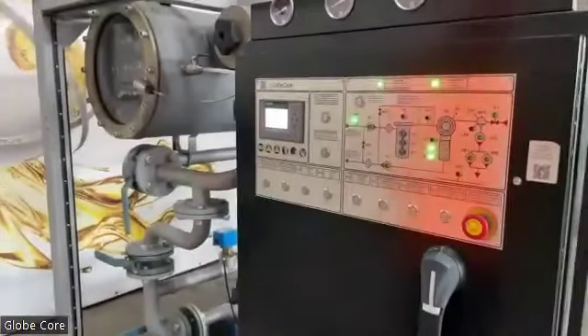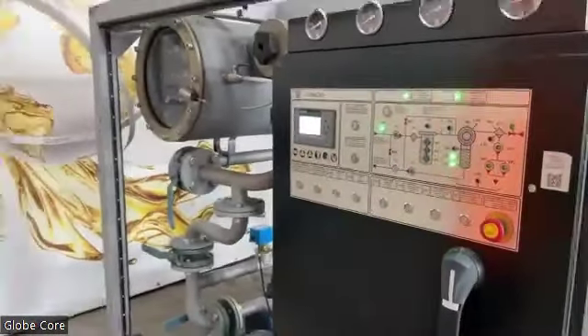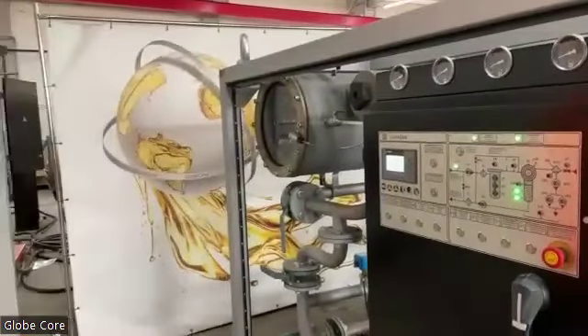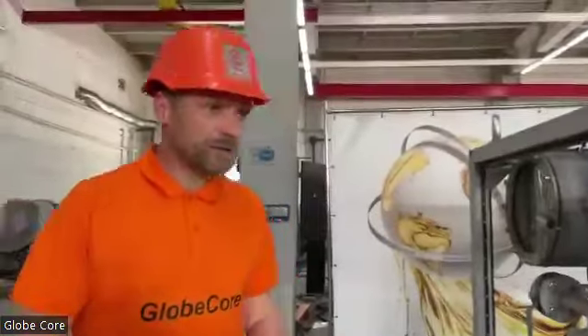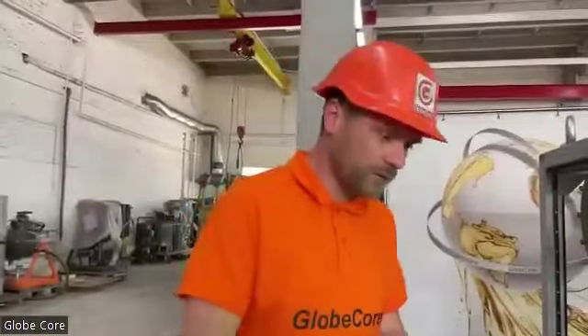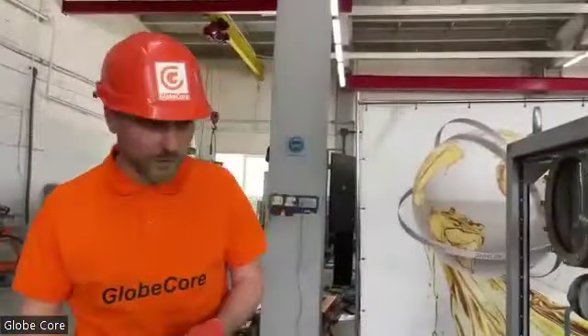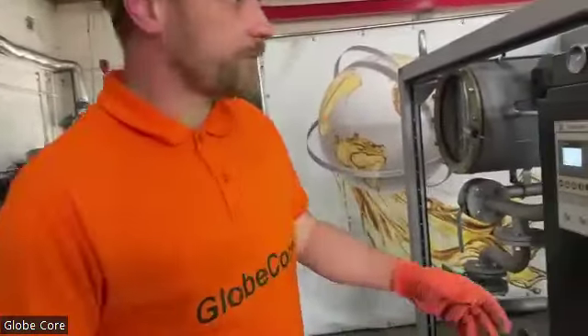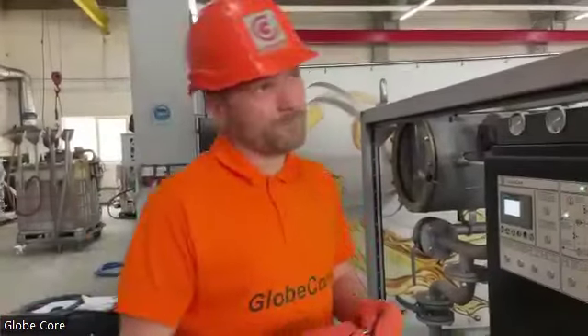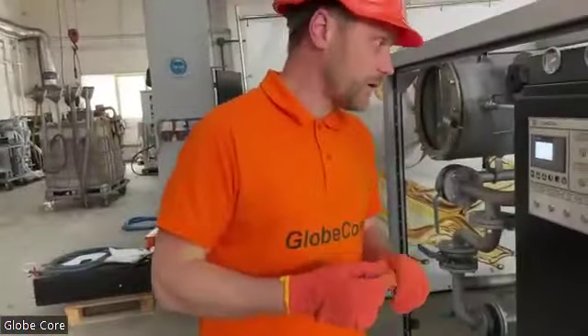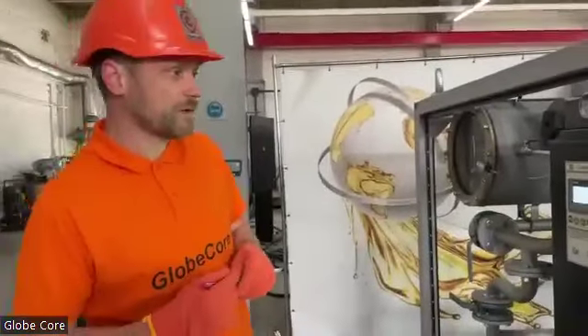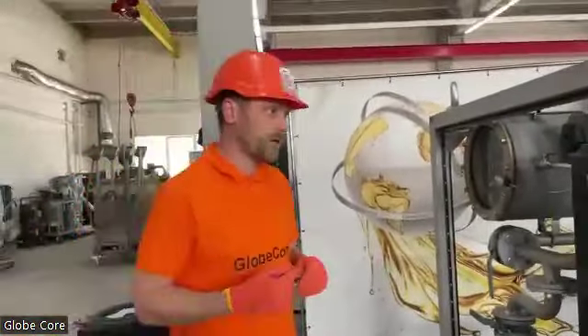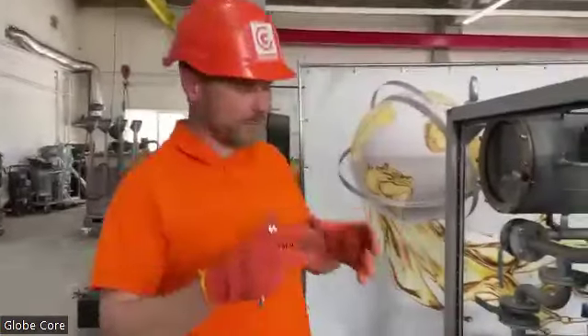Now, about this starting procedure and commissioning, it's very important to prepare the field for it. To start the unit, you need to arrange the proper electrical connection, availability of the cable. It is quite important because the total capacity of this unit is something like 180 kilowatts. So to run the unit on the full capacity, you need cable of 4 wires, each of 150 square millimeters cross section. So it should be quite a huge one.